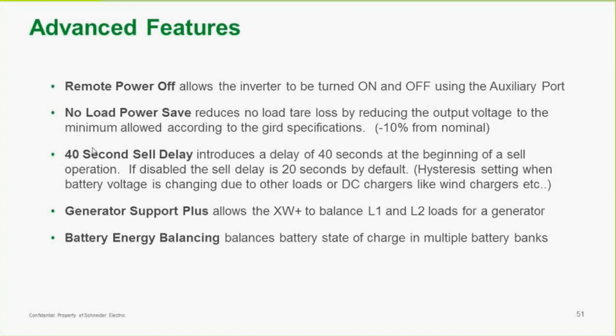That's there because if you have loads that are affecting the battery voltage, it provides a bit of hysteresis, and the inverter will wait for the battery to show a consistent low voltage or a consistent time to support the grid for 40 seconds, and if it's there, then it will do that operation. So it's both in and out of grid Sell. There's also generator support plus, which allows the XW Plus to balance L1 and L2 loads for a genset. And there's battery energy balancing, which balances the battery state of charge in multiple battery banks. All of those are advanced features, and all are available through the XW Plus with the right kind of configuration tools.